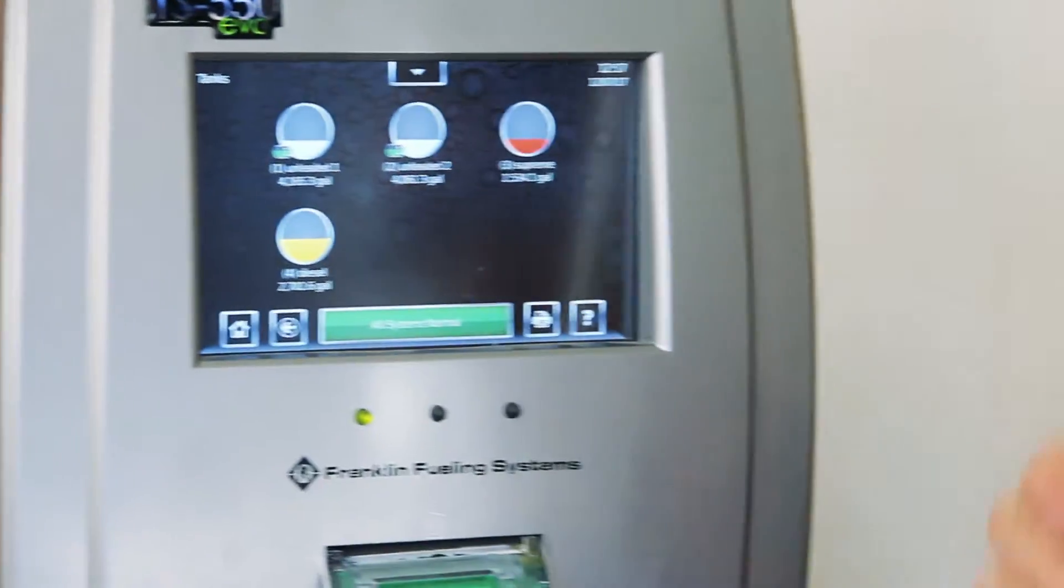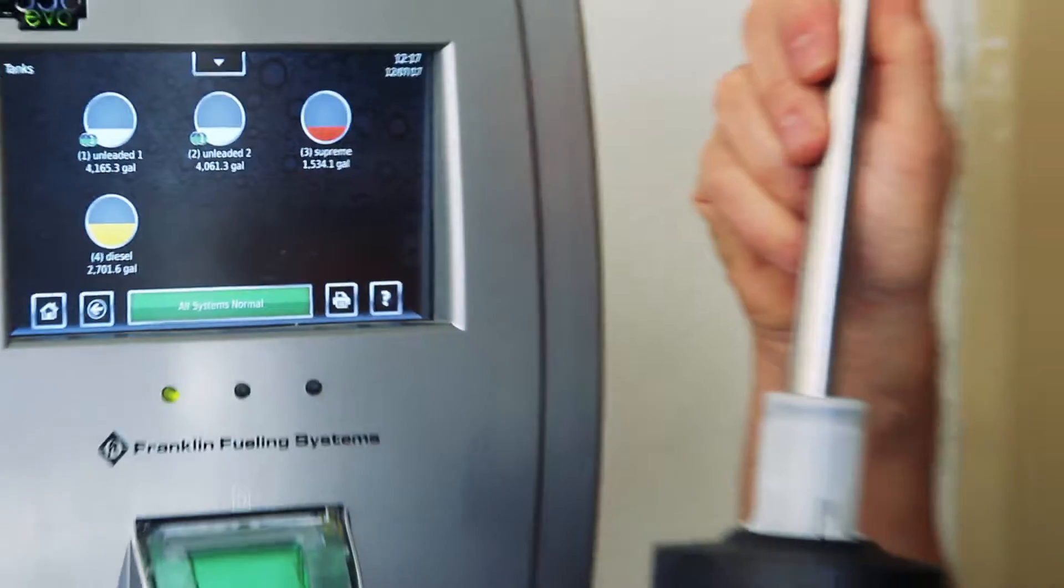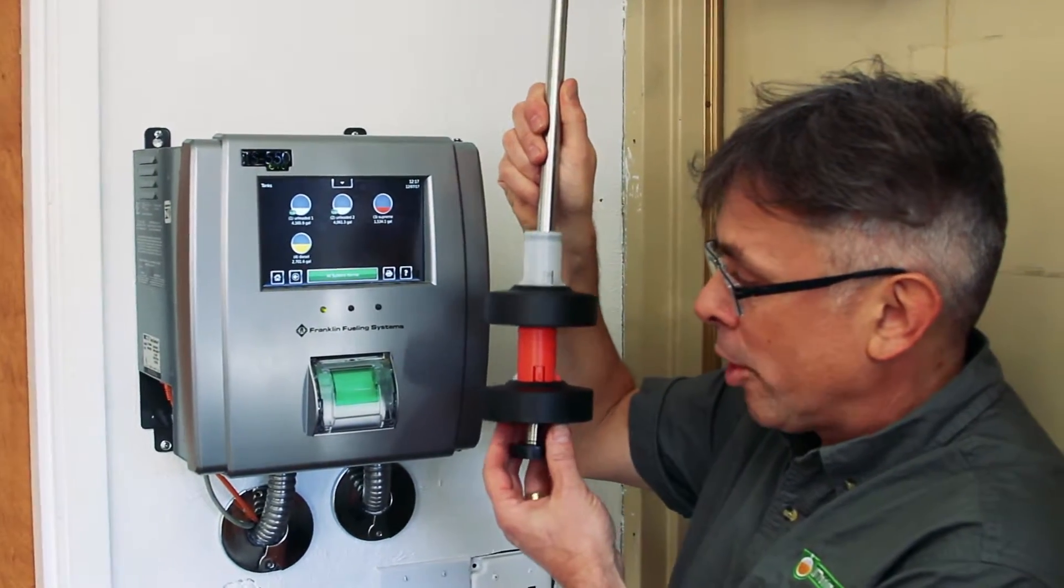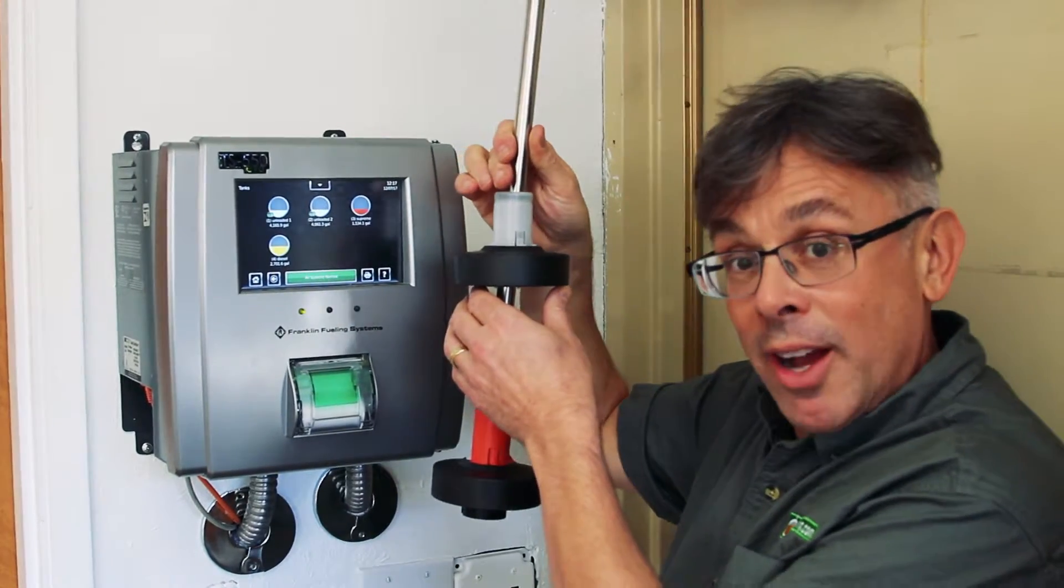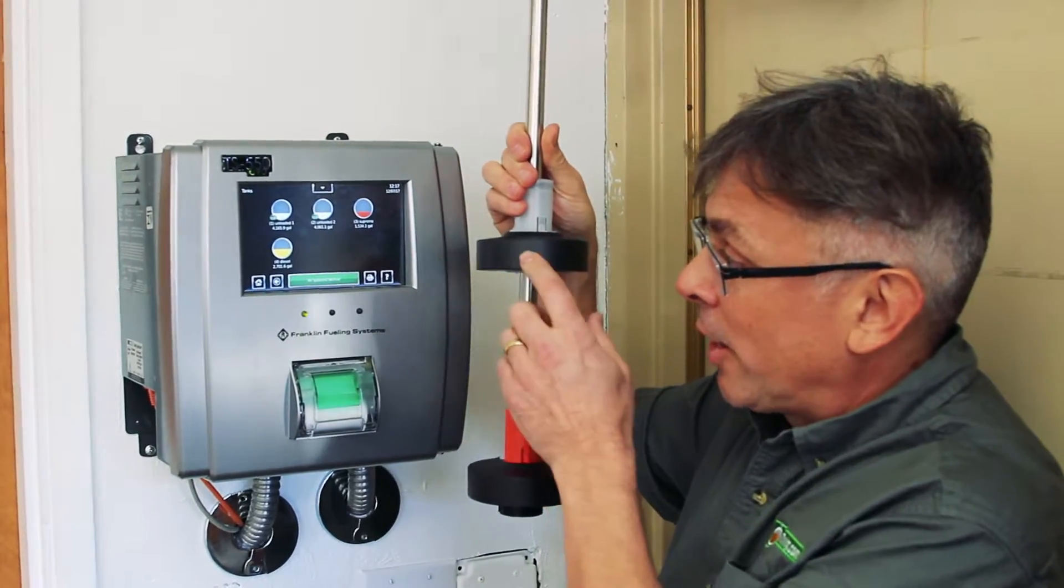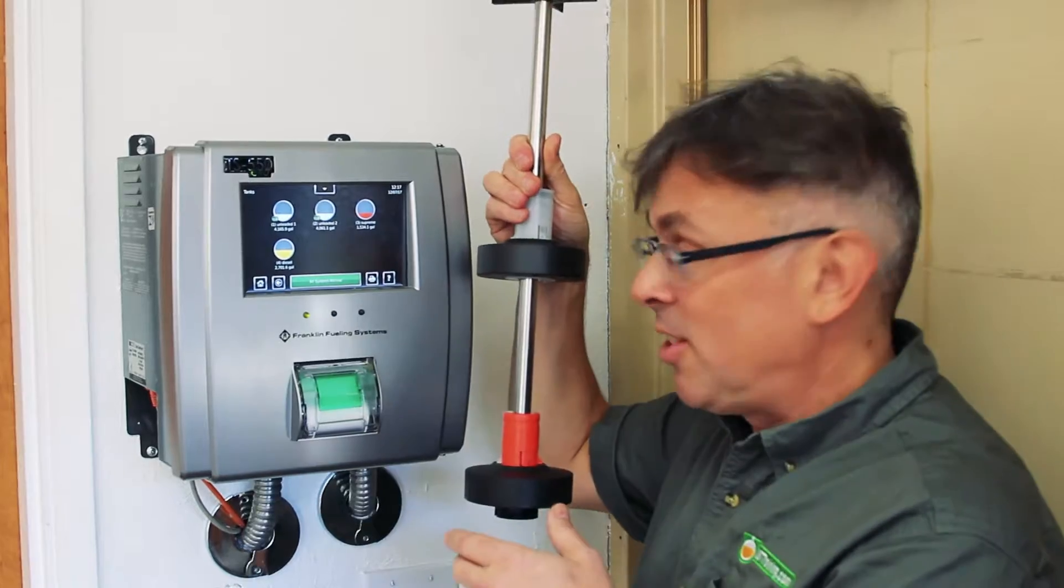There's actually a probe inside an underground storage tank. There's a bottom float for water and another float for fuel. And so as the liquid level rises, say during a delivery, that electronic information is then sent back to the tank gauge.